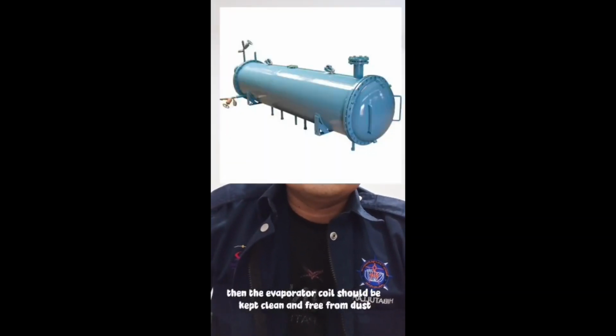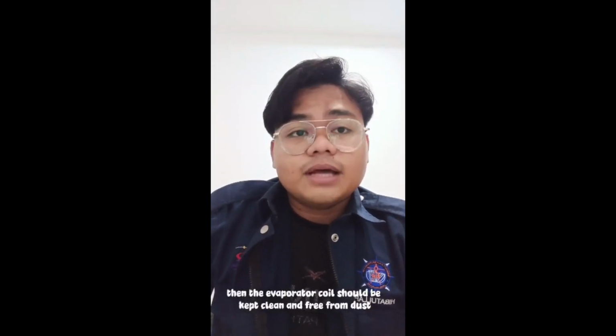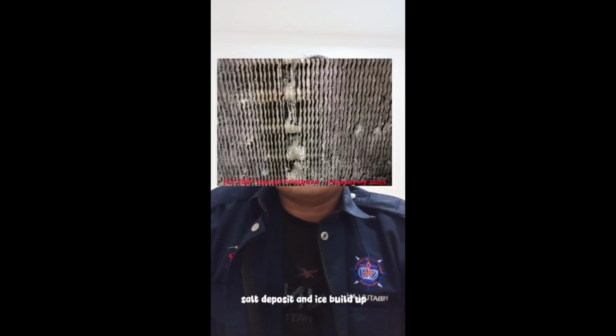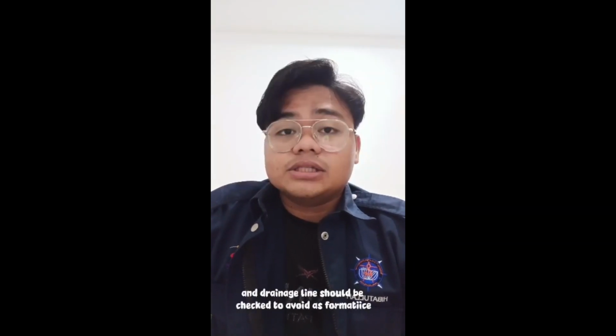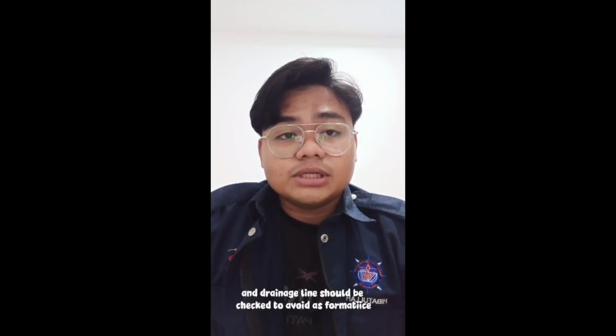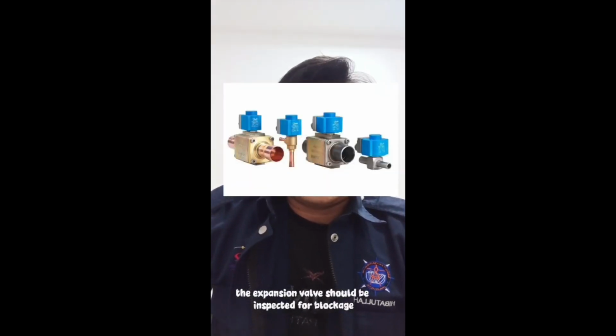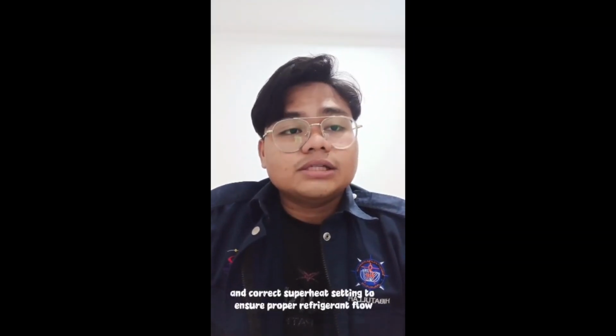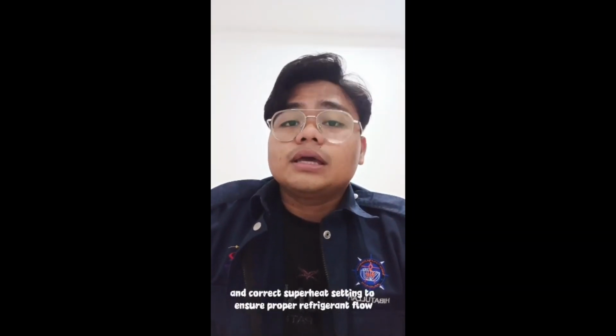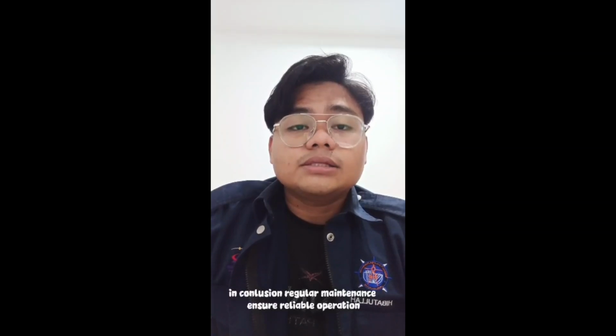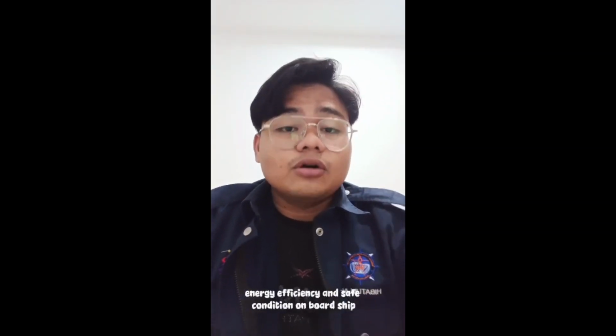Then, the evaporator coil should be kept clean and free from dust, salt deposit and ice build-up. The defrost system and drainage line should be checked to avoid ice formation and water flow problems. Finally, the expansion valve should be inspected for blockage, leakage and correct superheat setting to ensure proper refrigerant flow. In conclusion, regular maintenance ensures reliable operation, energy efficiency and safe conditions on board the ship.